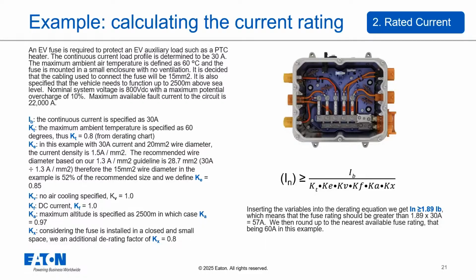Now we plug these values into the derating equation, and the result shows that the required fuse rating I sub N is greater than or equal to the continuous current divided by the product of all the subfactors. Doing the math for this example, the fuse rating needs to be greater than or equal to 1.89 times the continuous current. So I sub N is greater than 1.89 times 30 amps, which is 56.7 amps. We then round up to the nearest available standard fuse rating, which in this case is 60 amps.